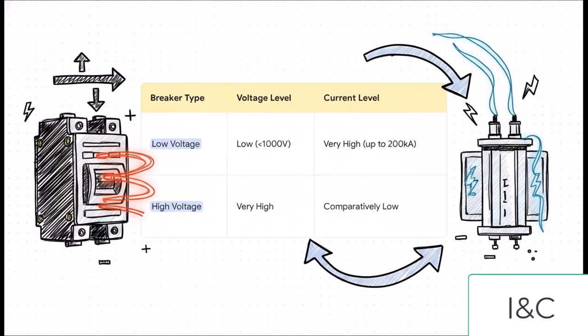This table here shows a really fascinating trade-off in electrical engineering. Think of it like a river, okay? High-voltage systems are like a narrow, super-fast river. You've got high pressure, but maybe not a huge amount of water flowing at any one time. Low-voltage systems, they're the exact opposite. They're like a huge, wide, slow-moving river. Low pressure, but a massive volume of water. So to deliver the same amount of power with lower pressure, or voltage, you need an absolutely immense volume of current. And that is why these breakers have to be built like fortresses.